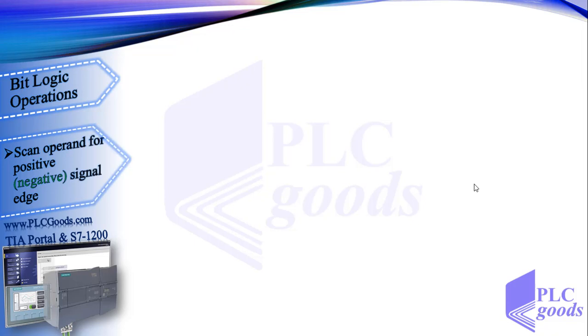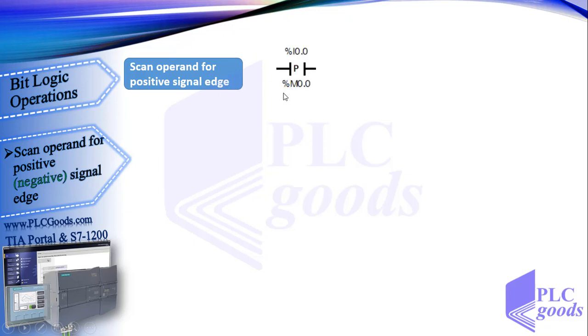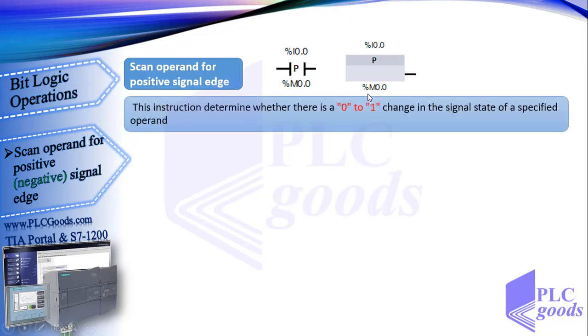Now let's see the first instruction: scan operand for positive signal edge. This is its ladder symbol. As you see, this instruction needs two addresses. It determines if there is a zero-to-one change in the state of the I0.0 address. This instruction needs a bit memory address to work — here M0.0 is used. This is its FBD symbol.